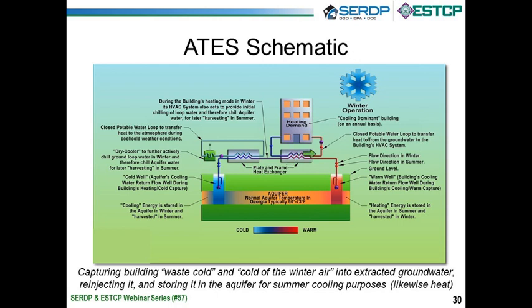The building then takes that heat and extracts it. It's not illustrated here, but there are heat pumps inside the building pulling heat out of the water all the time, so there's a heating demand in the building. The building is cooling the water, and therefore we're cooling the groundwater. That's the waste cool that we capture. But we're in the deep south, and we need a lot of cool and don't have a lot of winter. So, as illustrated, it could be a cooling tower, dry cooler, or adiabatic dry cooler, we further cool the water with the dry cooler at night and in the wintertime. The building might even be shut down, and we salivate when we see a rare 20-degree day in Georgia, and so we might try to make some 38-degree water to inject down.